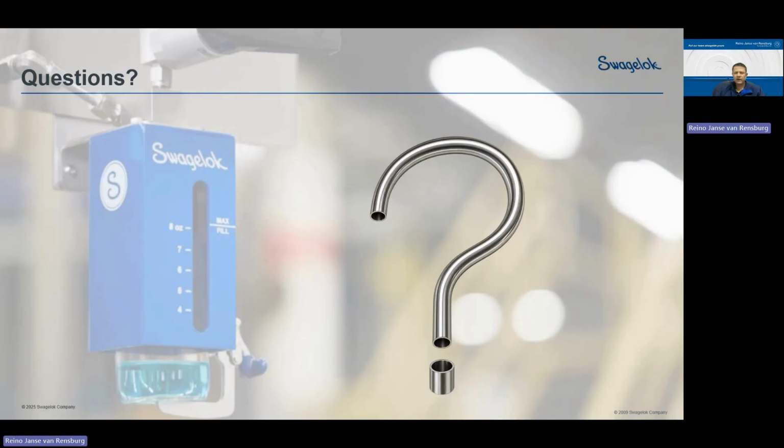Yes, you just basically need an outlet port, but with stacks it becomes a bit more complex, because a lot of stacks don't run at a positive pressure. That's the only challenging thing with stacks. We need to figure out how we get the sample into the cylinder, or however you want to sample it. Probably a cylinder, because it's toxic gases in a stack. It's a bit more tricky. You can't just suck it with a pump. The problem is you can suck the sample, but once you close your valve, the suction stops. So stack sampling with grab sample cylinders requires a bit more conversation.